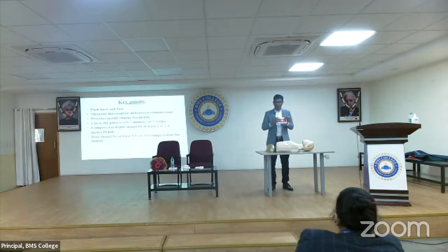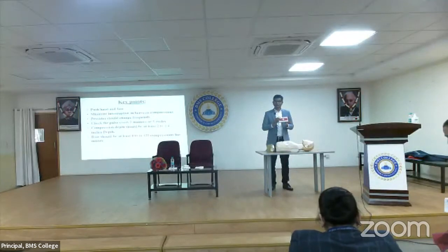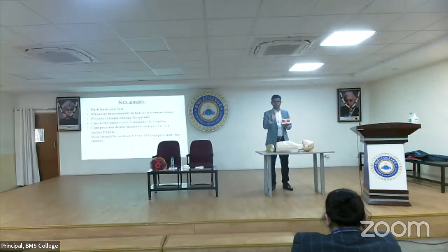The moment you plug into the AED, it will take a few seconds. It will not take more than 10 seconds. Why? If you delay more than 10 seconds, the brain will suffer a hypoxic injury. That is the reason it is designed in such a way that it will not take more than 5 to 10 seconds to analyze the rhythm, and it will advise shock only if it is required.